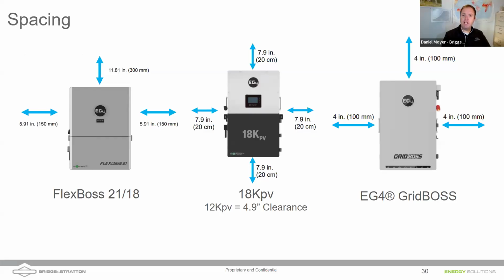With the 18K PV, a little bit different design, and we do need to have that air clearance on the bottom to vent out. GridBoss, again, though, it has no clearance limits on the bottom. Also, the GridBoss has knockouts on the back side of the cabinet. So if you really want to get a nice clean install, hide all the wires inside of a wall, you absolutely can do that with those GridBoss knockouts on the back side, which I really like.